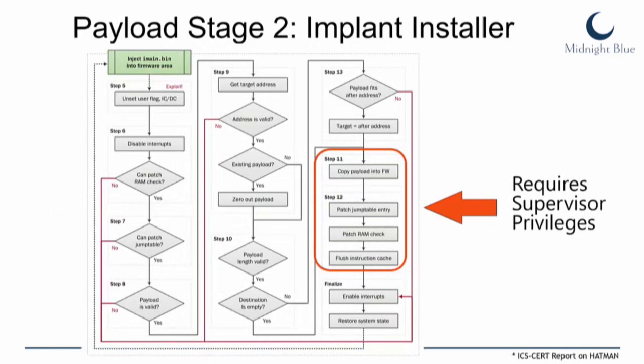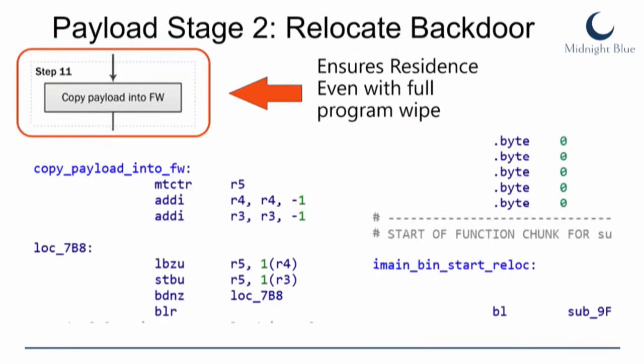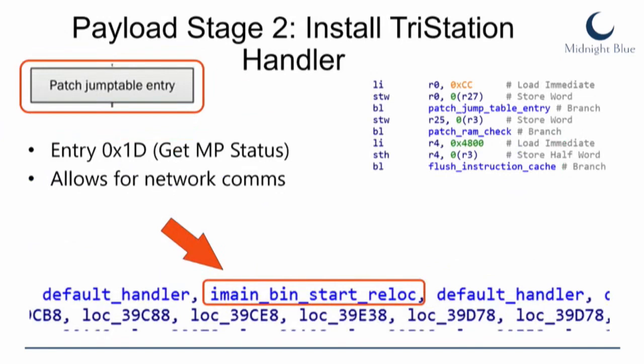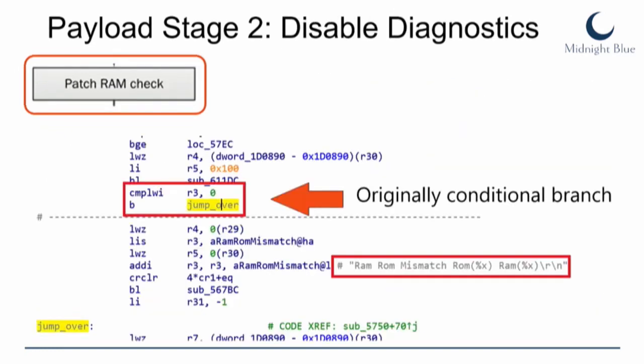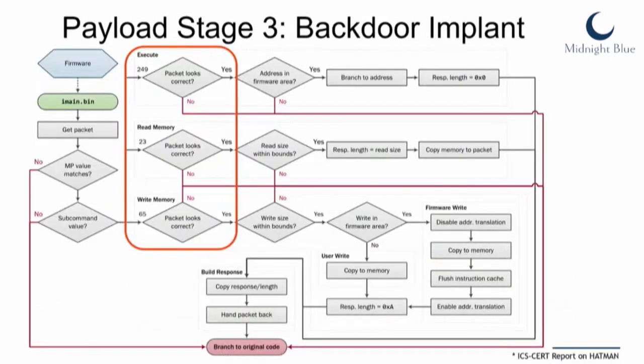And that allows us to do these next steps, to install the implant. The first is copying the payload into the firmware area of memory, which allows us to achieve residence even if they wipe all the safety logic on the controller. Then we patch an entry in the jump table, which allows us to hook a network command and invoke our implant when that command is called. And finally, we patch a certain RAM check, which was used for consistency between the firmware on ROM and in RAM, which would otherwise interfere with our changes.